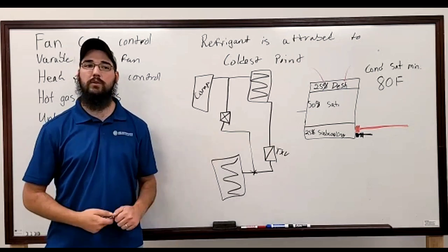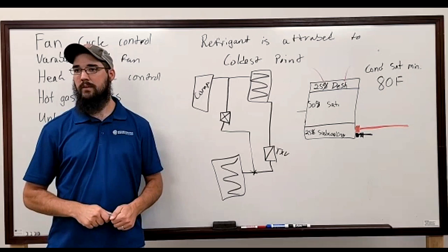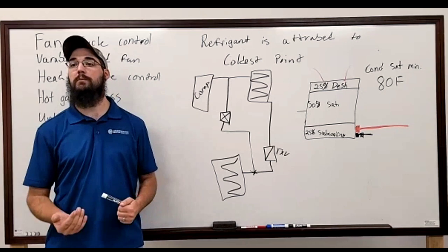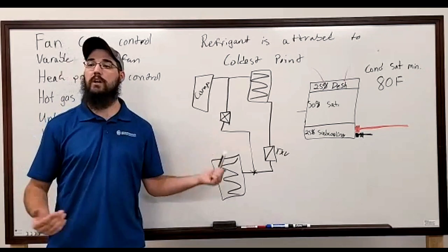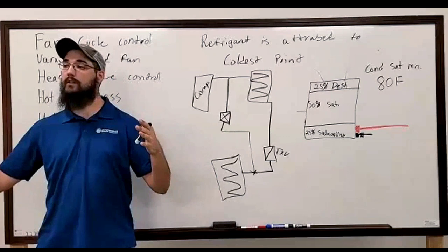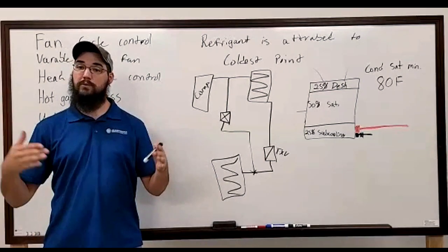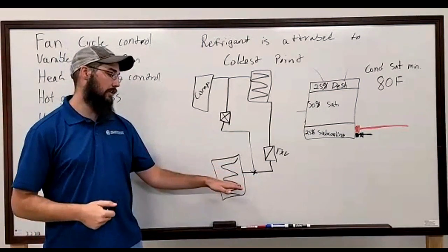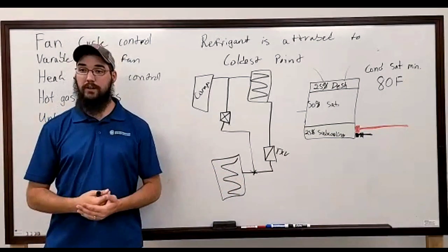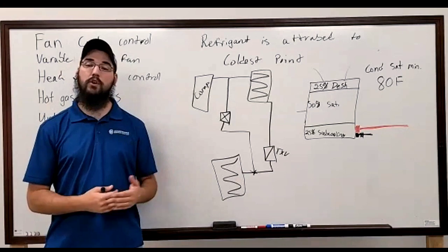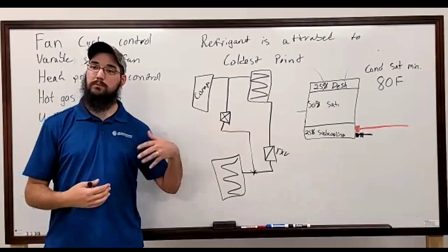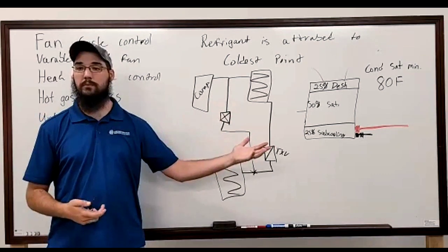That's why crac units are so common to use, because they typically are running a much lower return temp. So we have to introduce hot gas bypass. We're still moving the same capacity to control the load. But what will happen is these coils a lot of times will be oversized for pulldowns. So to compensate for the oversizing, the hot gas bypass will provide that additional BTU input.